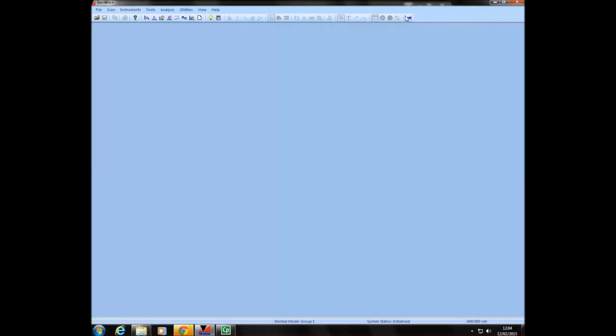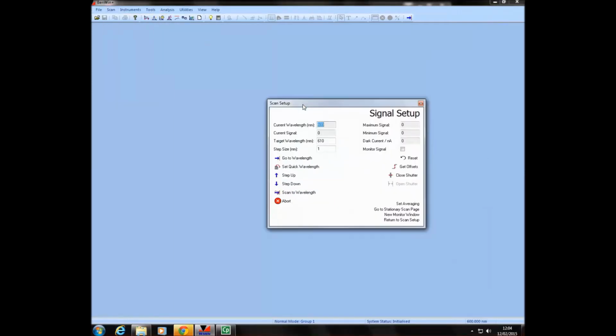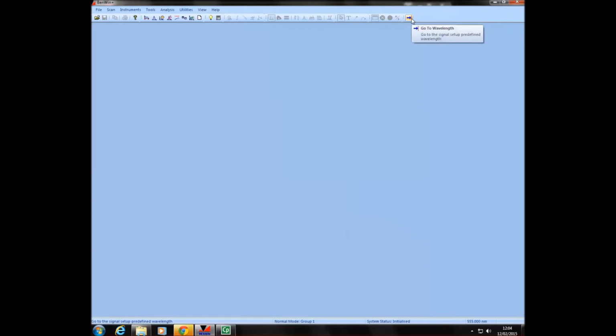This go to wavelength function allows you to set the monochromator to transmit a previously defined wavelength. Alternatively, one can go to scan signal setup or follow the signal setup shortcut to input a target wavelength. So for example, 555 nanometers in the green, we can set quick wavelength to define to which wavelength we go by hitting this button.